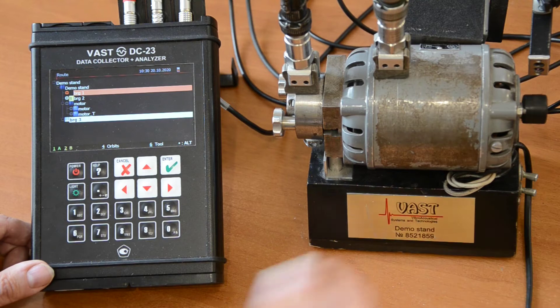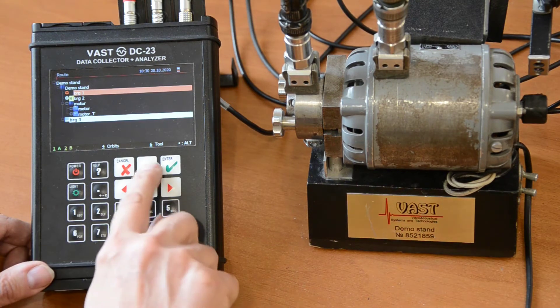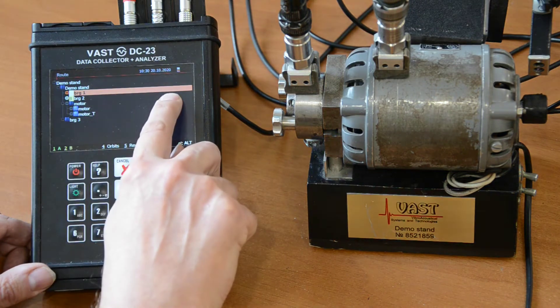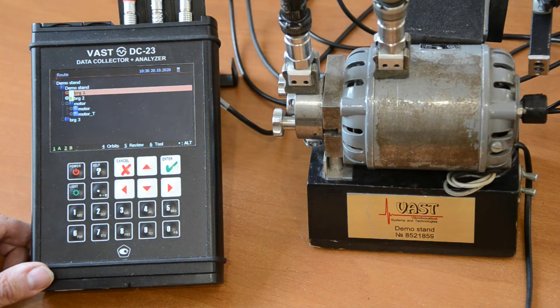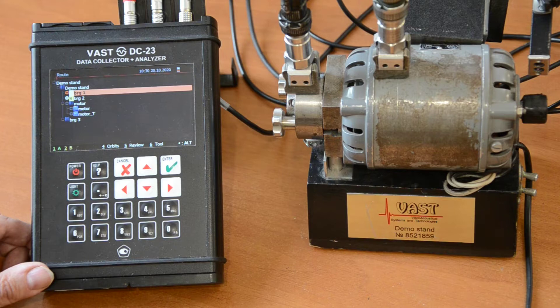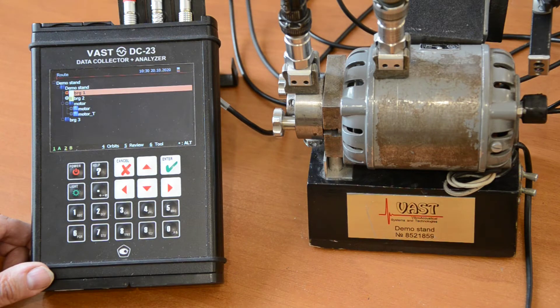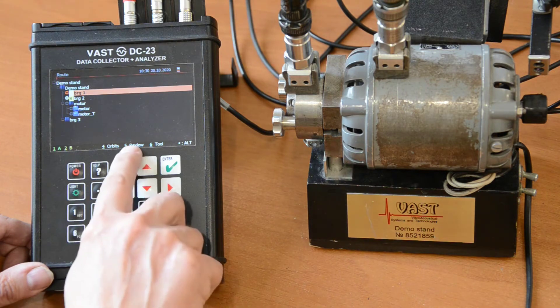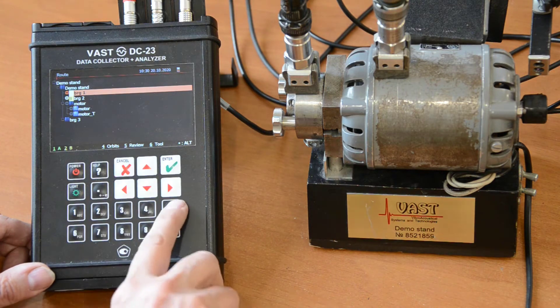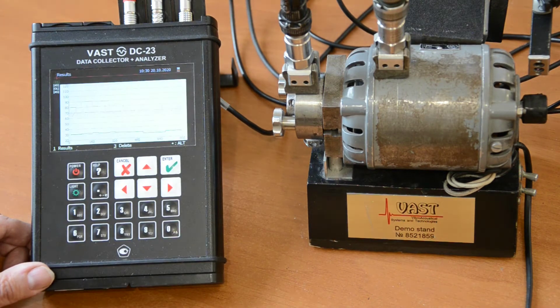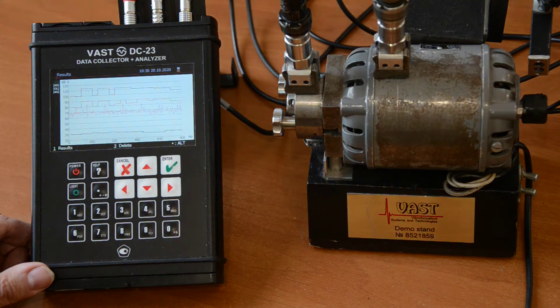I switch off the machine so that we can hear each other. So what we see here, first of all, is that we have an alarm. We have an alarm at this point. From where we get this alarm? This is the thresholds for the defects, for the condition that were downloaded from the computer. And if we go and see by the review button the measurements that we have here, we have a few measurements.